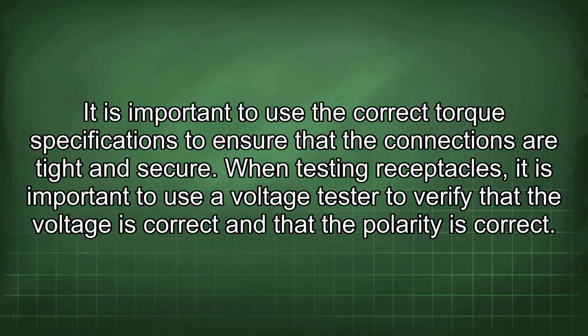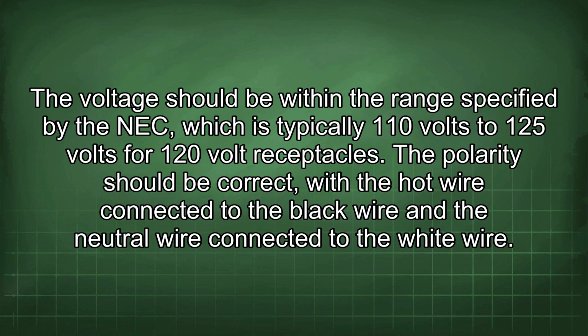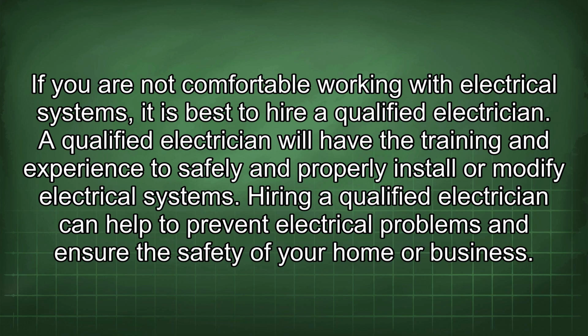When testing receptacles, it is important to use a voltage tester to verify that the voltage is correct and that the polarity is correct. The voltage should be within the range specified by the NEC, which is typically 110 volts to 125 volts for 120 volt receptacles. The polarity should be correct, with the hot wire connected to the black wire and the neutral wire connected to the white wire. If you are not comfortable working with electrical systems, it is best to hire a qualified electrician.